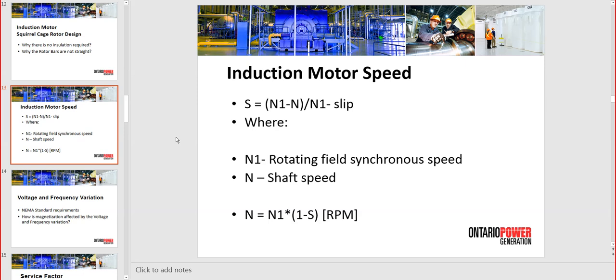However, it is changing with the load. So when you have a larger load, this slip increases. When you have no load, this slip decreases. Let's say you have a slip of 1.5%: at no load maybe 1, at full load maybe 1.7. So it's not a constant value, it's variable with the load.